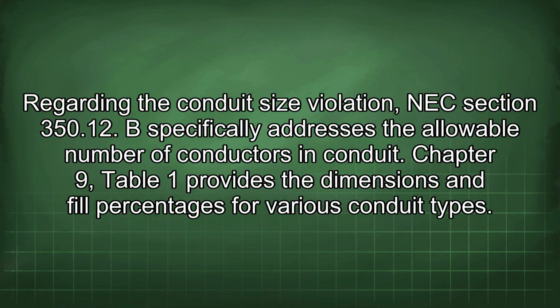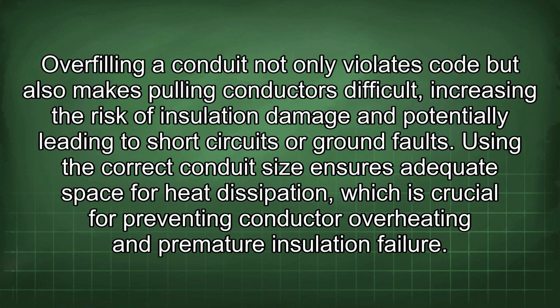Regarding the conduit size violation, NEC section 350.12 specifically addresses the allowable number of conductors in conduit. Chapter 9, Table 1 provides the dimensions and fill percentages for various conduit types. Overfilling a conduit not only violates code but also makes pulling conductors difficult, increasing the risk of insulation damage and potentially leading to short circuits or ground faults. Using the correct conduit size ensures adequate space for heat dissipation, which is crucial for preventing conductor overheating and premature insulation failure.